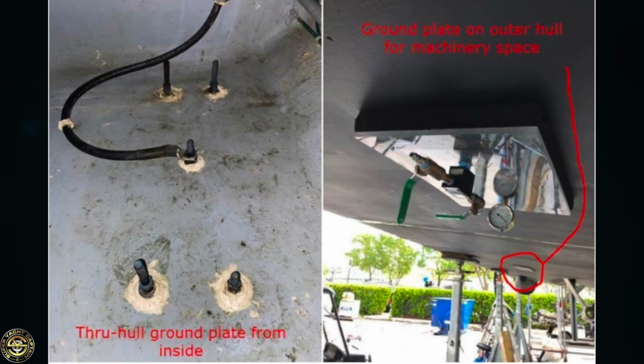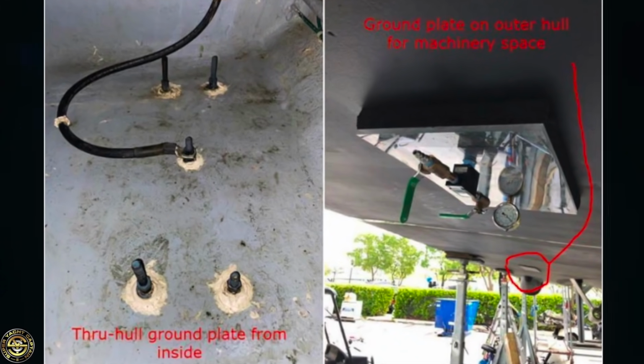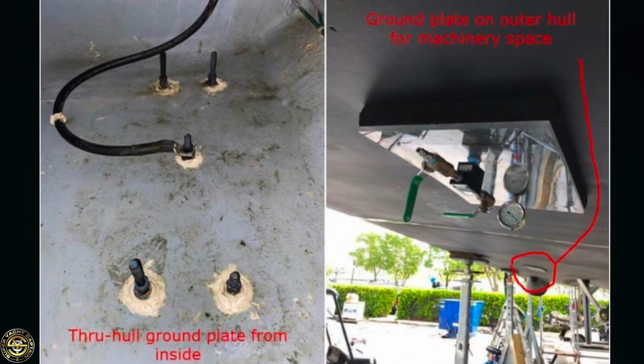The yacht utilizes a combined earth and neutral distribution where the neutral from the generators is connected to the earth bus bar in the switchboard. From the switchboard, this earth neutral is connected to an earth ground plate fixed to the exterior of the hull.